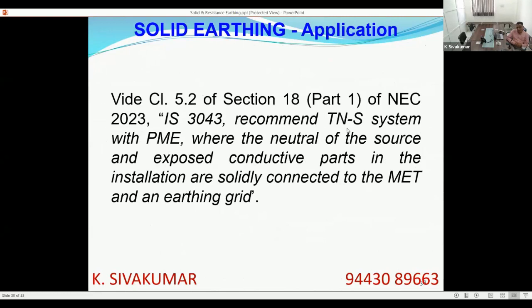Then the subsequent clause, 5.2 in NEC, says that in a TN-S system with protective multiple earthing, the neutral of the source, let us for a moment forget the equipment earthing, the source may be a transformer or a generator, the neutral of the source is solidly connected to the main earthing terminal and the earthing grid. That means even in IS 3043, for systems above 230 volt, solid earthing is recommended. Solid earthing is mandated, actually.